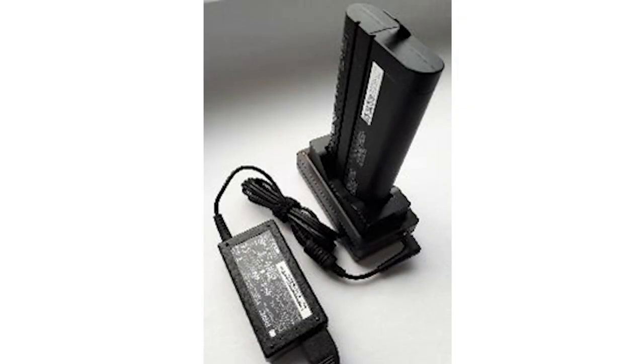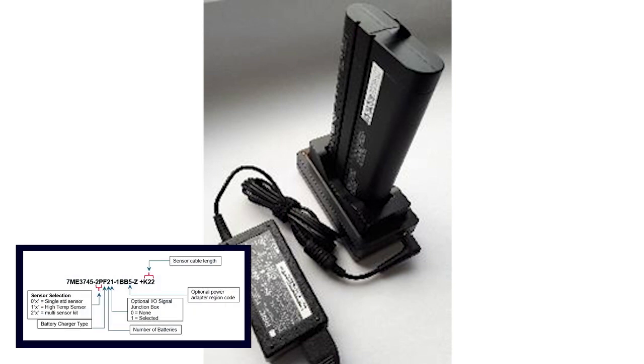The FS290 system is in use worldwide. Therefore, the supplied battery charger is selectable based upon your region and identified by the letter code in position 10 of the system part number. This meter indicates the letter code F, which is for use in North America.